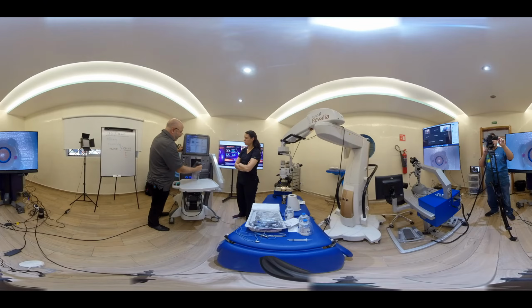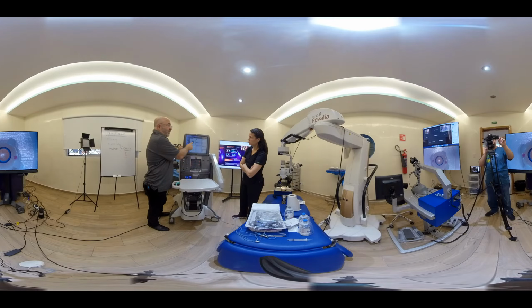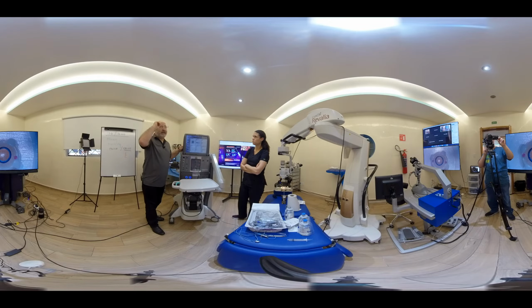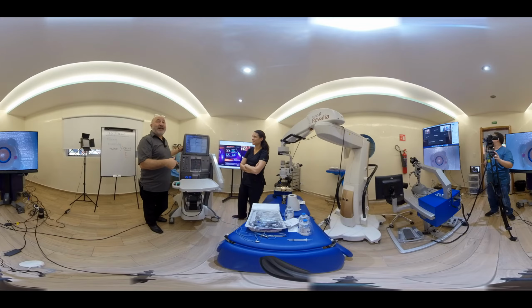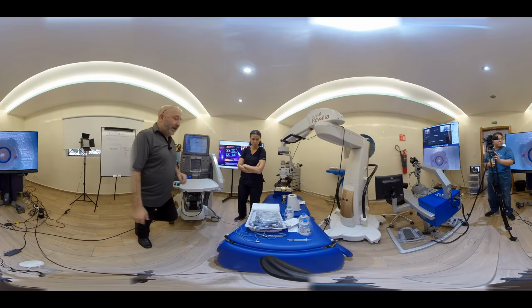We put it straight in. Many people put the bottom in first, but that's a mistake. Put it straight in, press, press, press, until the picture on the screen changes, and that's the time to let go. If you don't keep pressing, sometimes you'll get a false load. It looks like it's in, but then when you hang the BSS, fluid just keeps running and empties the bottle. Okay.